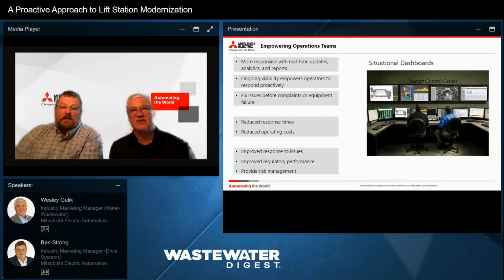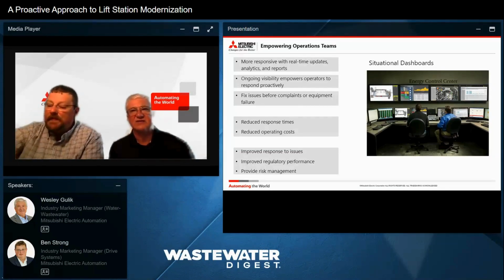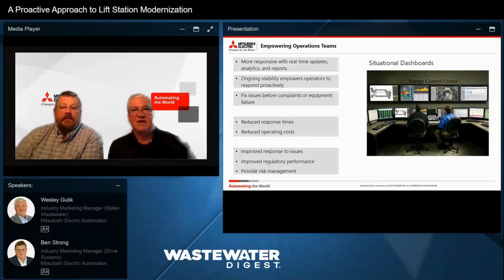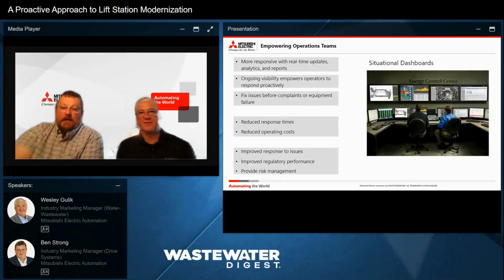So, kind of like what Ben talked about, more of the preventive, predictive maintenance, where there's a tremendous amount of information that you can gather from the variable frequency drive. But what do you do with that is a key discussion that's taken place during the last 3 to 5 years. Reduce response times, reduce operating costs, because again, it's already implemented in the system, and you typically can make changes, or there are changes already recommended in your SCADA system on how to correct that issue, which improves the response to issues and improves regulatory performance, as well as provides risk management, which is a very key point when we talk about SCADA.